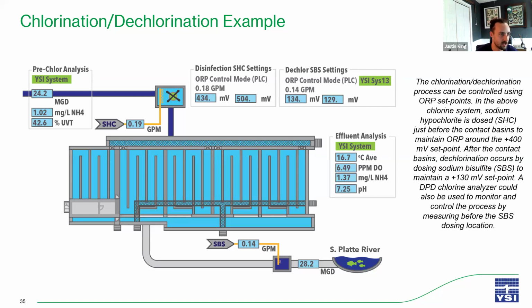And basically the way that a chlorination dechlorination system works is that we're going to dose, in most cases, sodium hypochlorite at the beginning, and then let the water flow through these contact basins. And then once we meet a desired residual, we'll start the dechlorination process, which is typically done by dosing, I believe it's sodium bisulfite, to remove chlorine before we discharge it, because there's typically a zero or close to zero discharge limit for chlorine when it's going back into the environment.